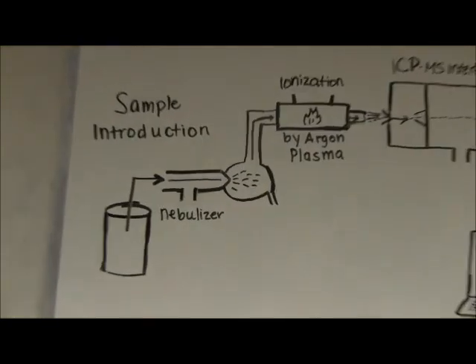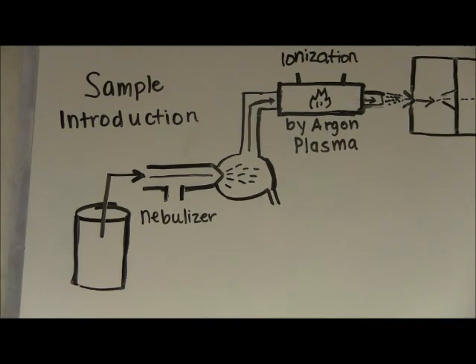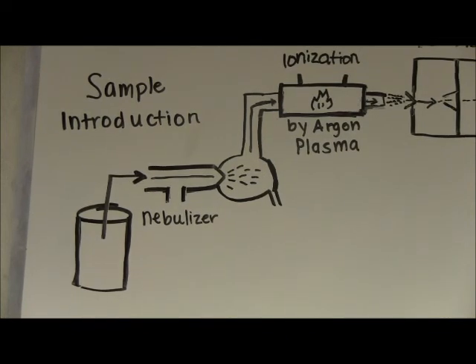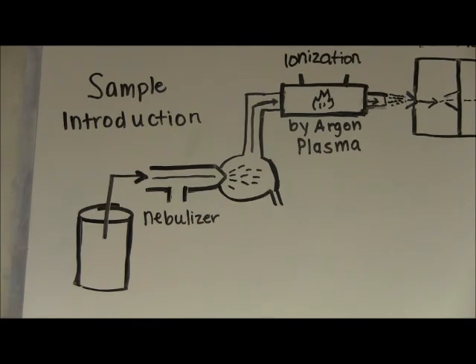Unlike the atomic emission spectrometer, ICP mass spectrometers can accept solid as well as liquid samples. Solid samples are introduced into the ICP by way of a laser ablation system which can usually be purchased as an accessory. Liquid samples are introduced by way of a nebulizer which aspirates a sample with high-velocity argon forming a fine mist. The aerosol then passes into a spray chamber where larger droplets are removed via a drain. Typically only about 2% of the original mist passes through the spray chamber.